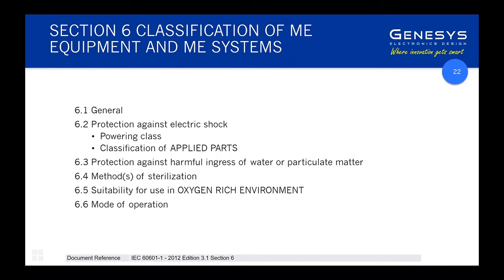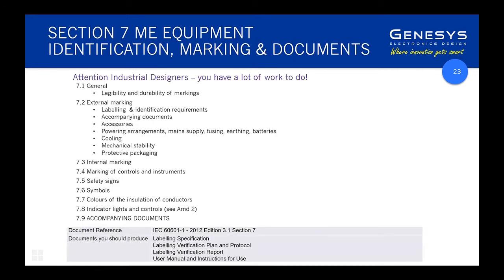You need to classify the equipment — the clauses that apply depend on the class of equipment. This generally differentiates mains-powered versus mains with earth versus mains isolated versus lower voltage versus internal battery, and also considers aspects such as sterilization or use in an oxygen environment like an oxygen tent, which increases fire risk. You need to work through this classification, as it in turn will activate subsequent clauses of the standard that apply to that particular device class.